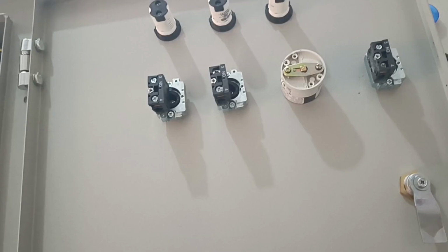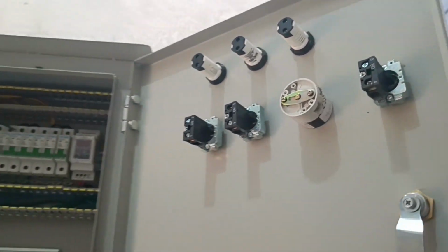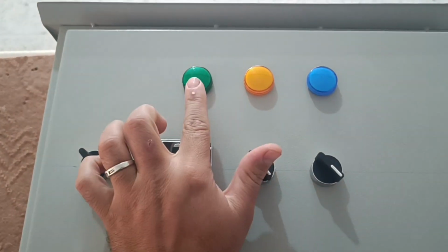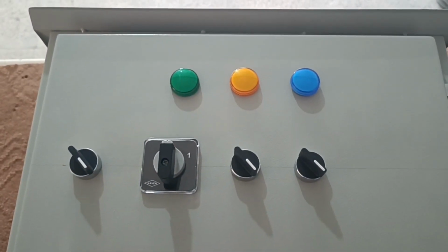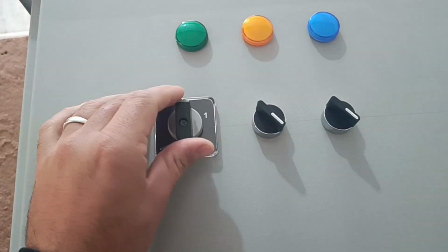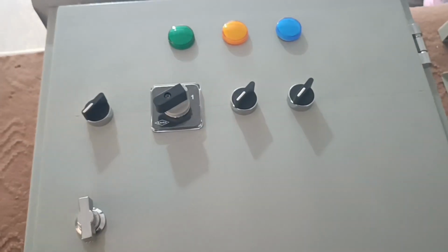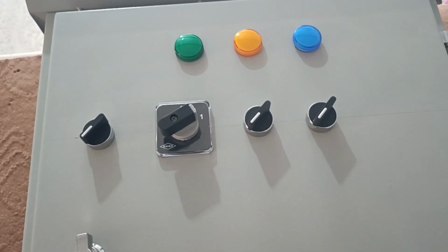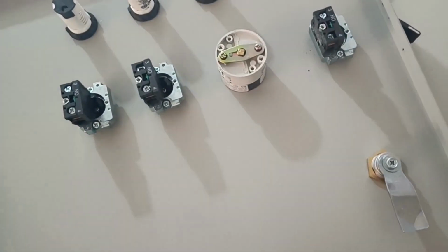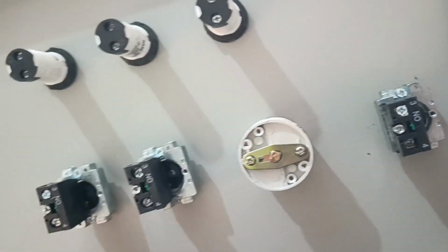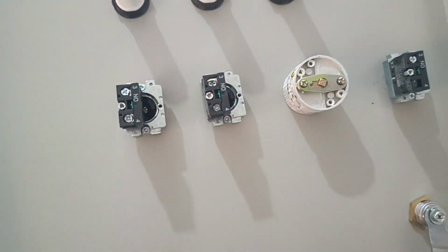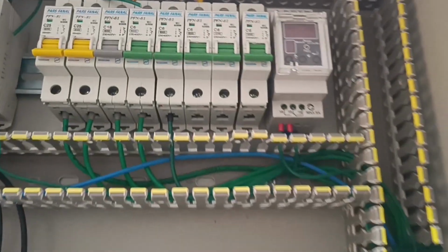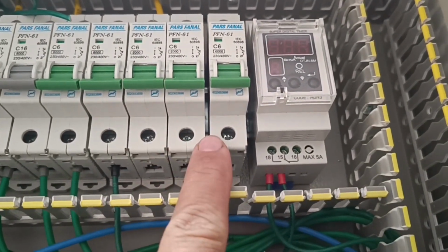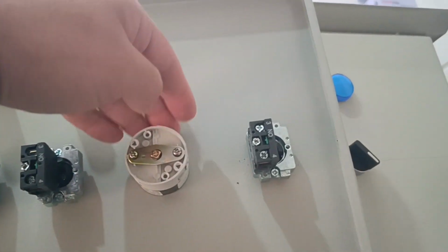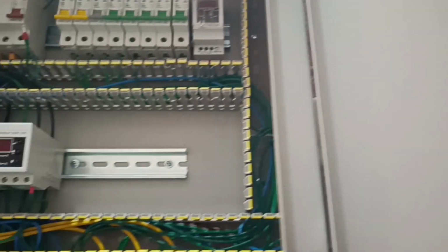To control the connection and disconnection of some outputs, we have installed several selector switches on the door of the electrical panel. Additionally, three signal lights indicate the active status of each phase. The inputs of these three selector switches are connected to the output of their corresponding miniature circuit breakers. And the output of each of them is connected to its corresponding output terminal.